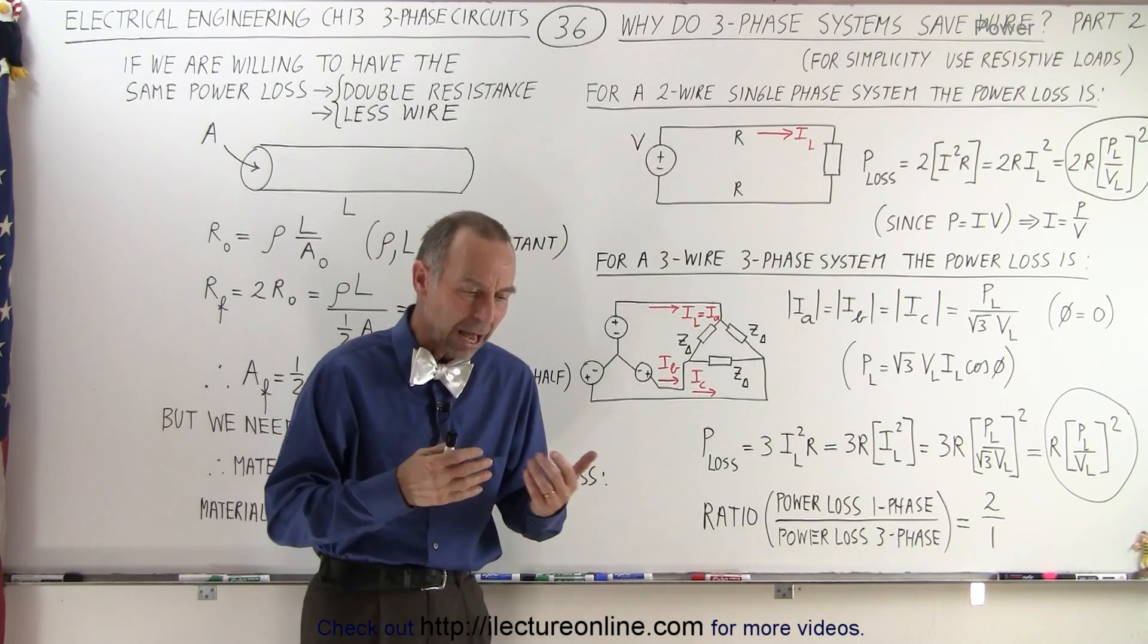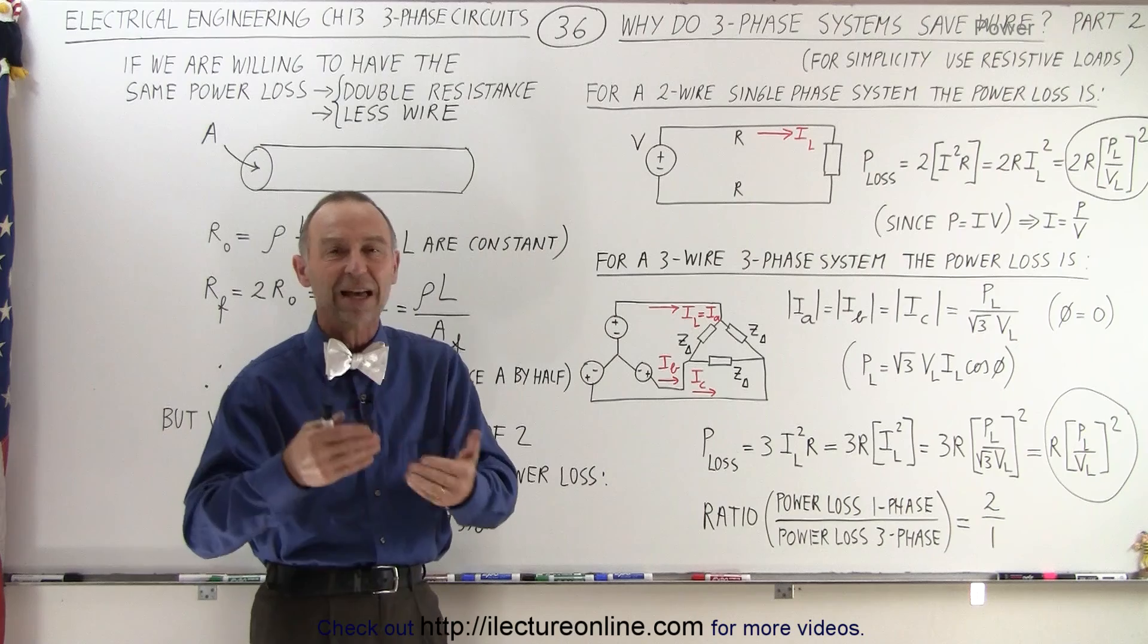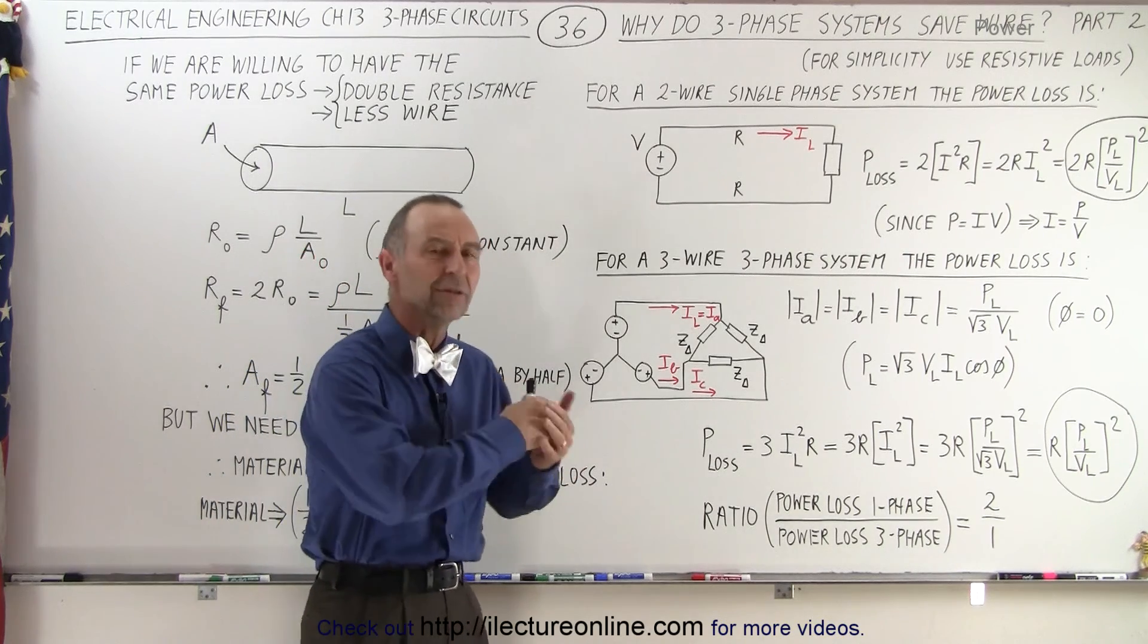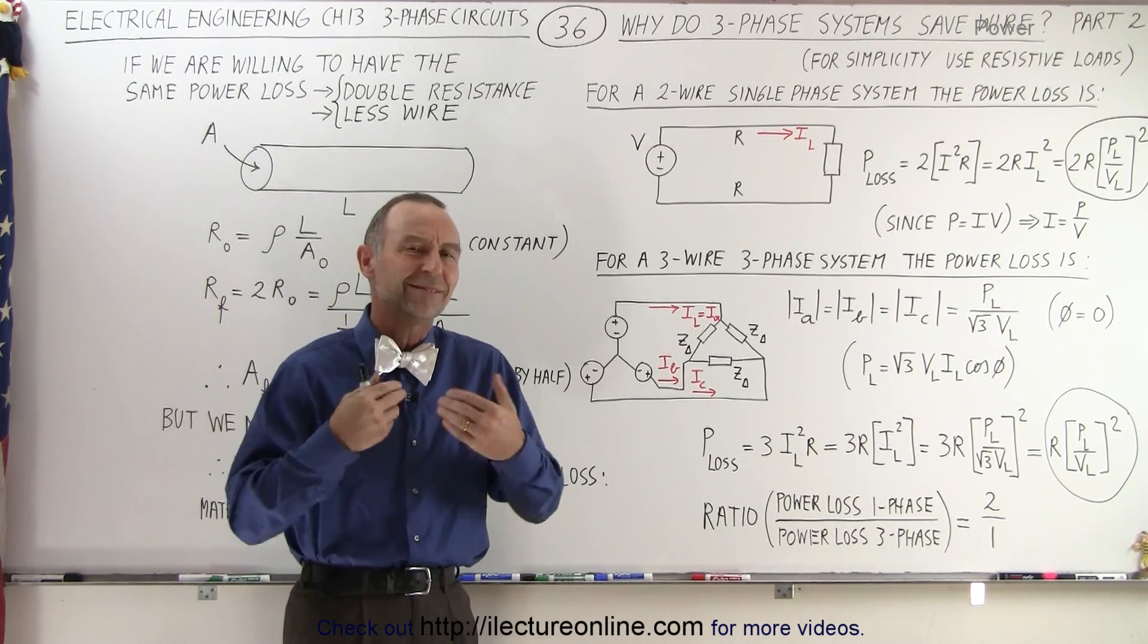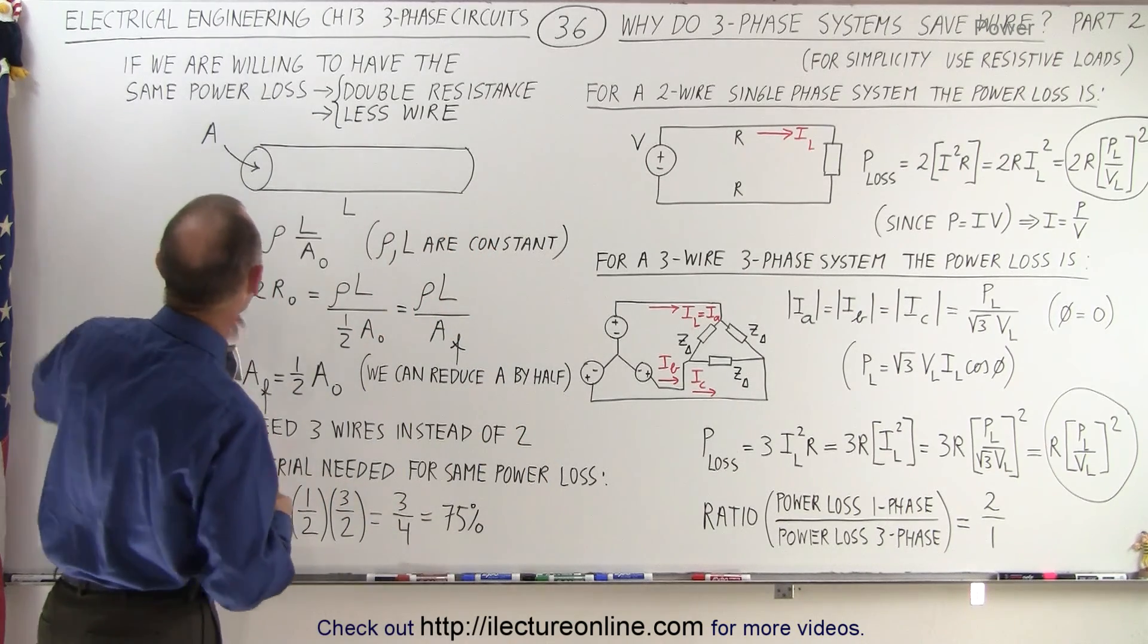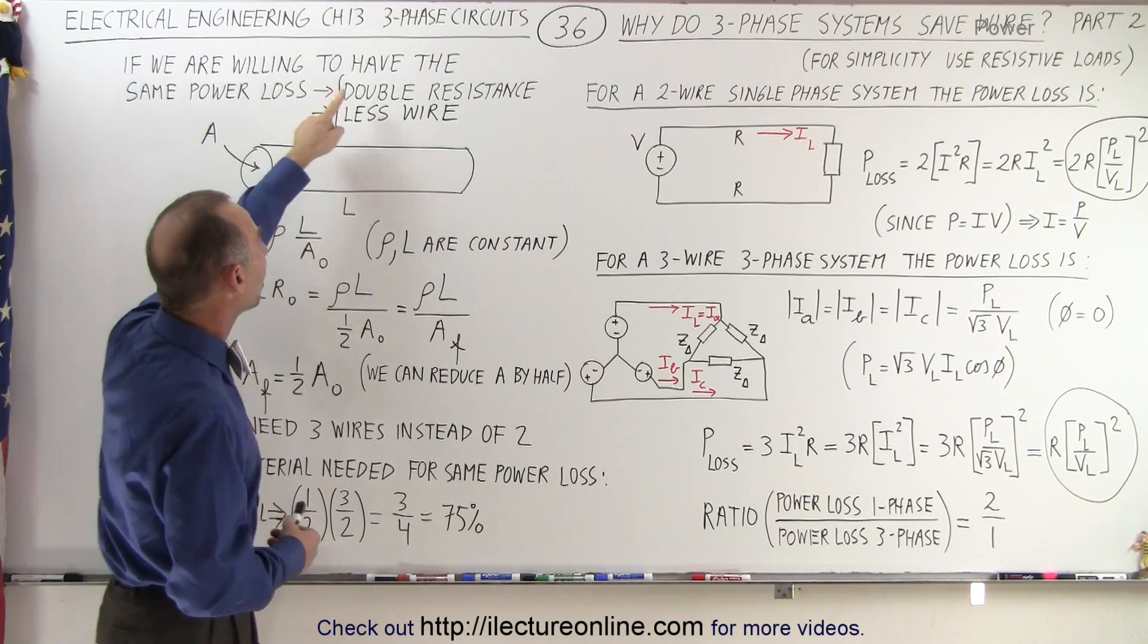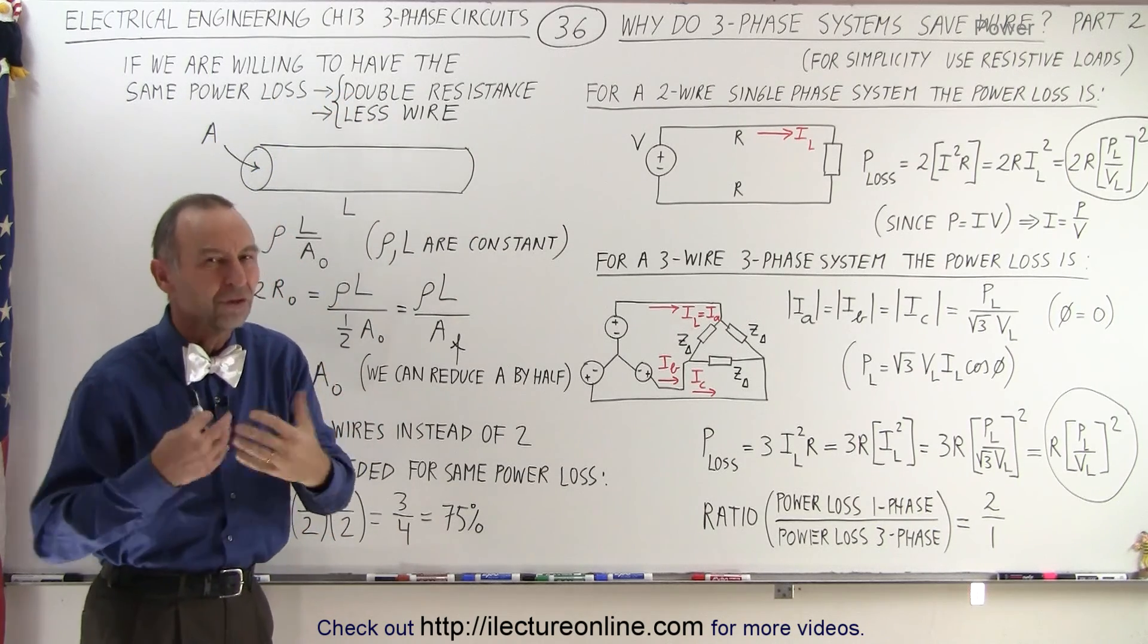So let's assume we now set up a three-phase system in such a way that the power loss is exactly the same as for a single-phase system. What would be the savings in the wiring? So if we're willing to have the same power loss, we can double the resistance by using less wire.